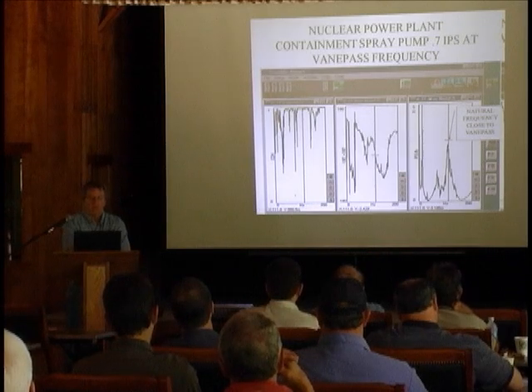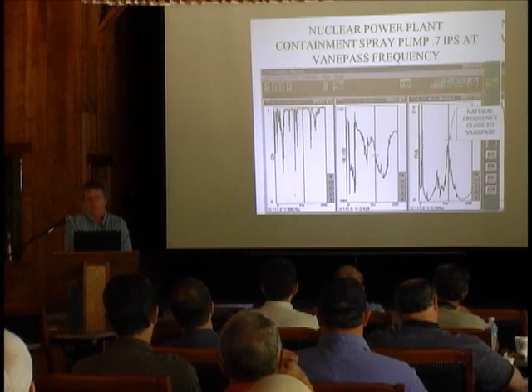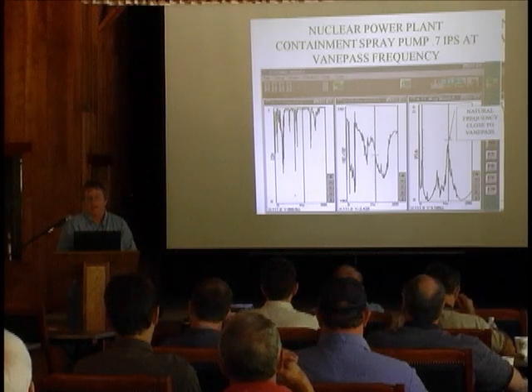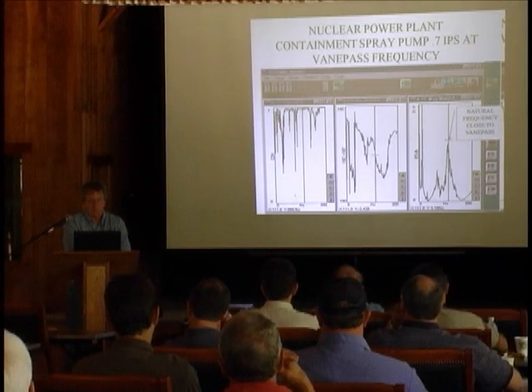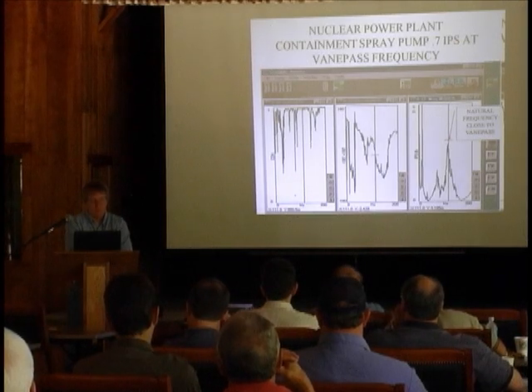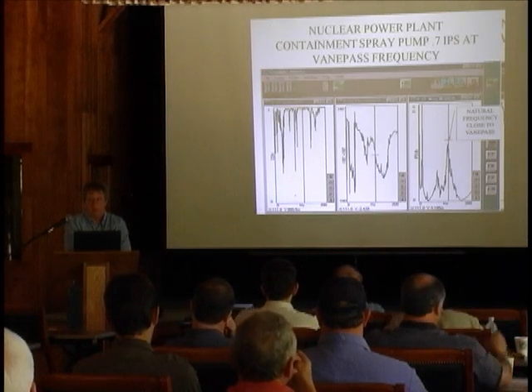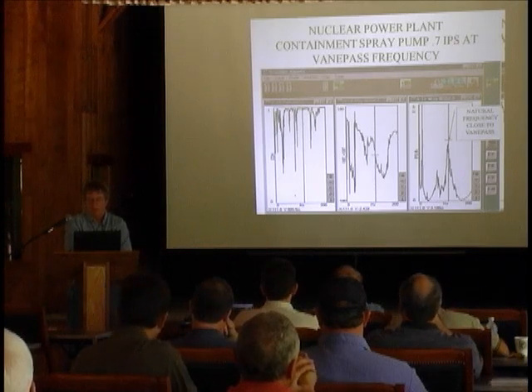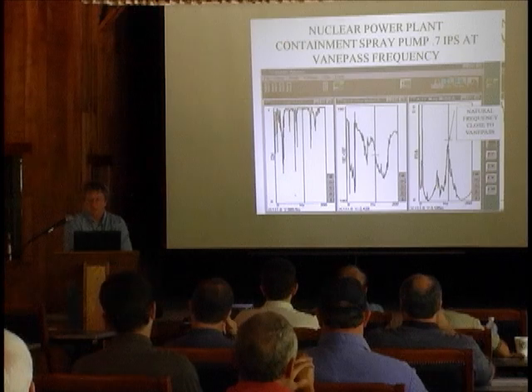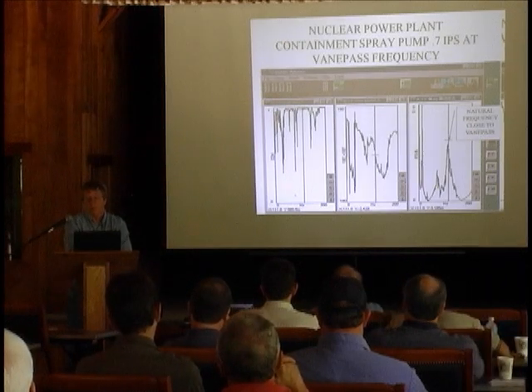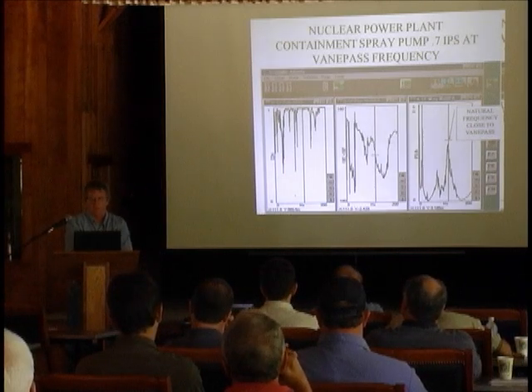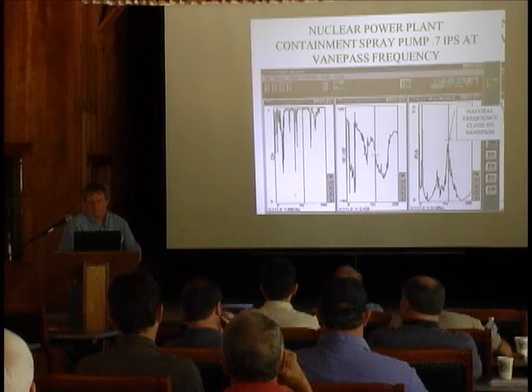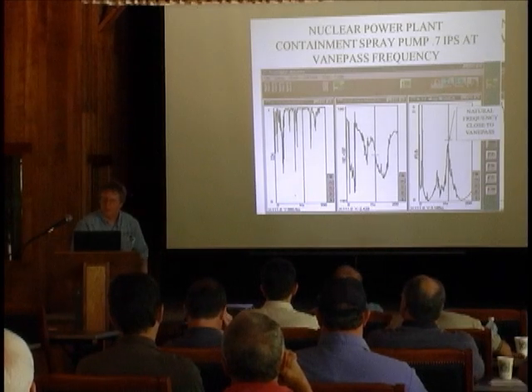So I'd warned them for years. I said, you've got a vane pass problem. You've got 4 vanes in that impeller. You really should change to a 5-vane impeller, and they didn't do it. And then they get in a bind, and once they get into what's called a tech spec violation, they have 72 hours to resolve the problem or they bring the reactor down. And that's like megabucks a day. So this is another one of those things where, if the number of people involved could have solved it, it would have been solved in about a minute. There were rooms of people. And again, they're always looking over and bothering you so you can't get your job done.